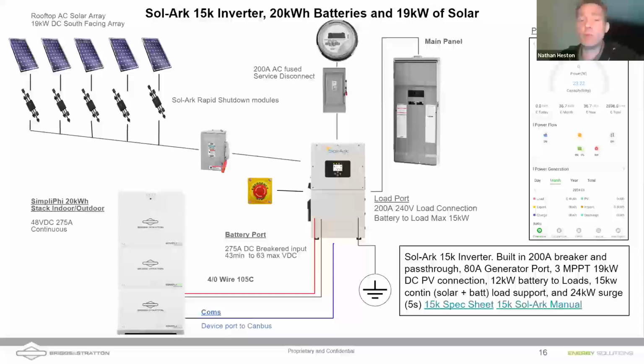But that would still leave your generator port open for you to be able to get that generator to work and be able to use the 2-wire start. If you want to use the generator port for AC coupled solar and a generator, then you would have to do a manual transfer switch if you want the 2-wire start to work. So I hope I've answered your question, Russ. It is a little bit more complicated.